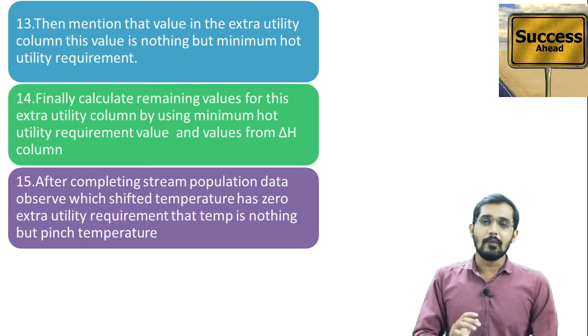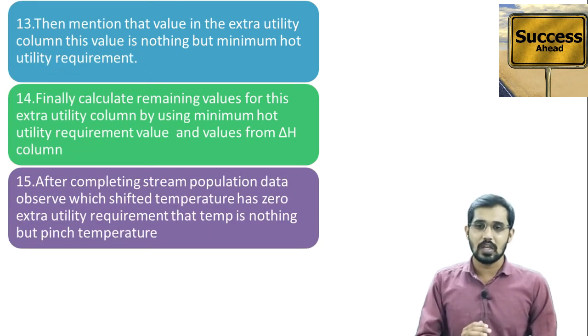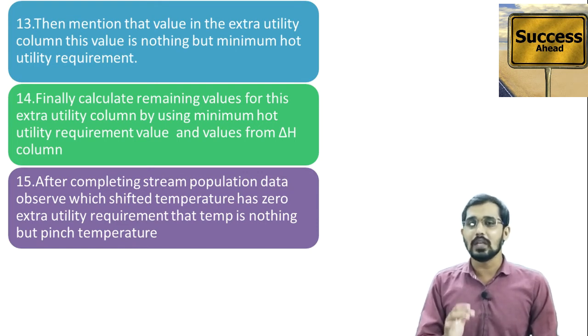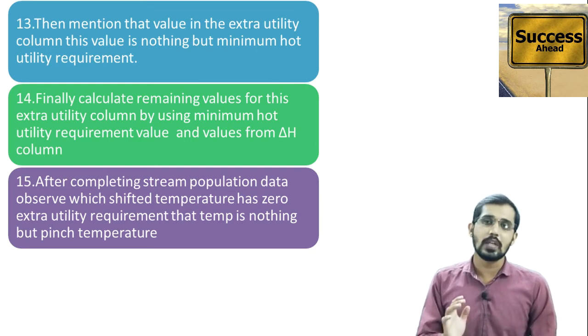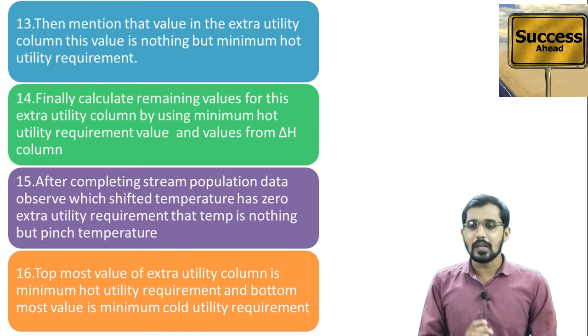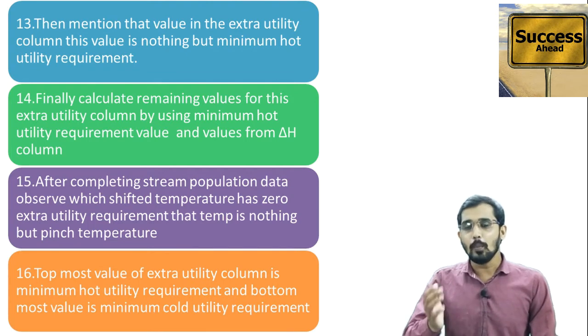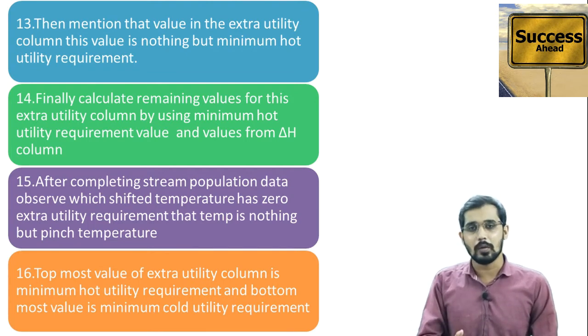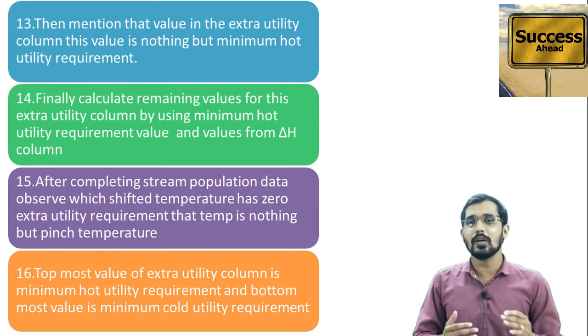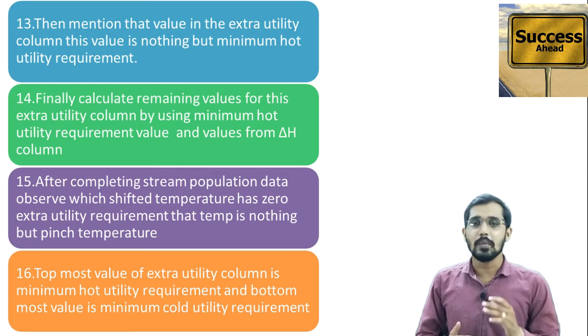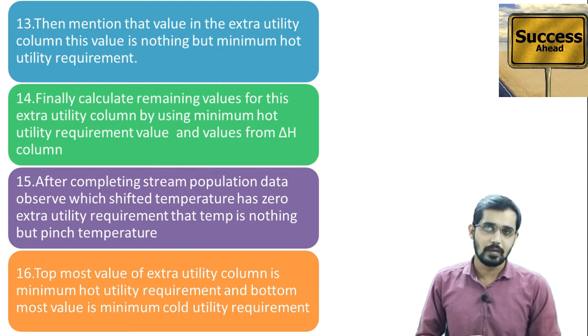After completing the stream population table, observe which shifted temperature has zero extra utility requirement — the corresponding temperature for that value is the pinch temperature. The topmost value in the extra utility column is the minimum hot utility requirement, and the bottom-most value is the minimum cold utility requirement.